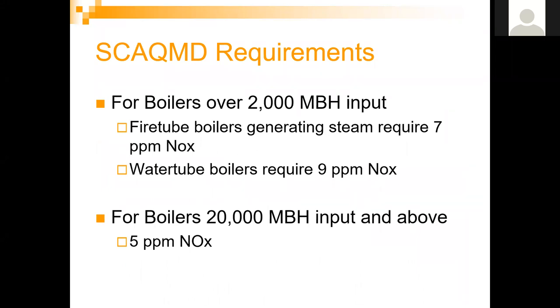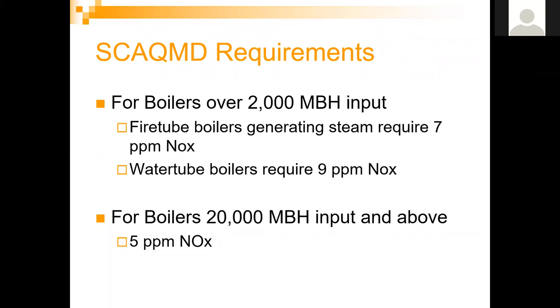For boilers over 2,000 MBH input: fire tube boilers generating steam now require 7 PPM NOx. This is a new requirement as of the end of 2018 — previously it was 9 PPM for both water tube and fire tube. At the end of 2018, the South Coast AQMD did a BACT determination — best available control technology determination — and determined that fire tube boilers generating steam had proven they could operate at sub-7 PPM, so they changed the regulation down to 7 PPM NOx specifically for fire tube boilers generating steam.